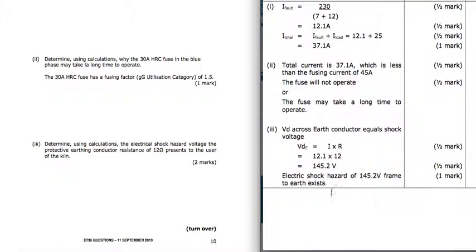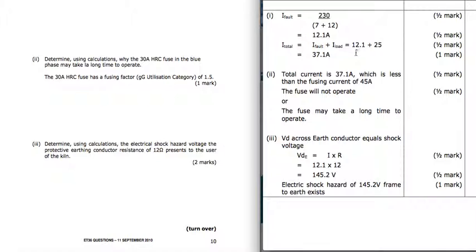Determine, using calculations, the electric shock hazard voltage the protective earthing conductor resistance at 12 ohm presents to the user of the kiln. So current flowing through 12 ohms is going to cause a volt drop, so we could get a shock from that volt drop. So the volt drop is going to be I times R, V equals I times R. We've got 12.1, which is our fault current from back here. So 12.1 times 12 gives us 145.2 volts. So there's a shock hazard of 145.2.